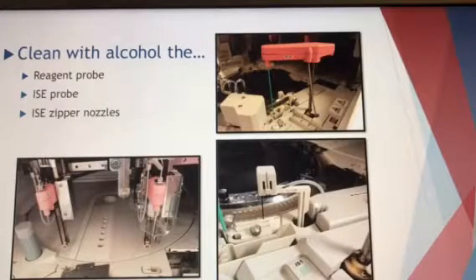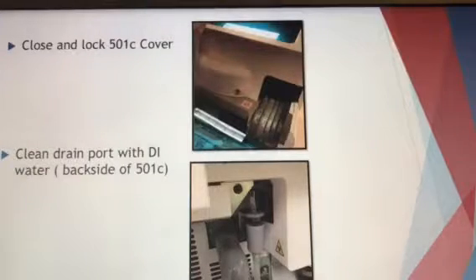And then again, you're going to clean the reagent probe, ISE probe, and ISE zipper nozzles, and they're all pictured there. And down at the bottom, you have your 2 reagent probes. Up at the top right, you have your ISE probe, and then down at the bottom is your zipper nozzles. All right, and then you are done with the manual cleaning for the 501 side. So you're going to make sure you close that cover nice and tighten the lock.